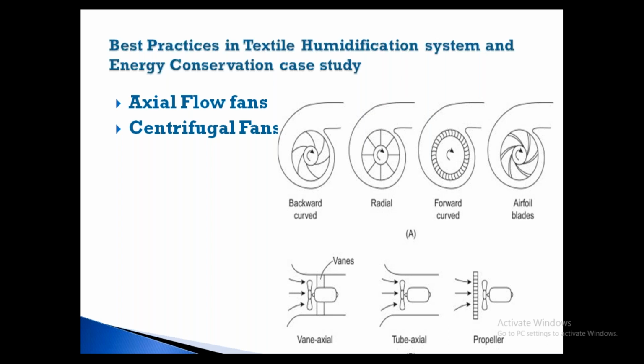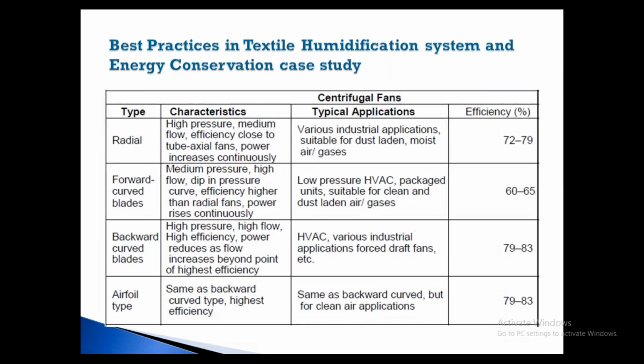If you take the axial flow fans, we have three types: one is vane axial, then tube axial, then propeller fans. Propeller fan is least efficient, vane axial is the most efficient one. So the selection of the fan is important, not only for finding the power of the HVAC plant. You would have seen two identical plants, and you would have taken the readings and power calculation for the particular mill or process. But you need to note which type of impeller fans they used. It is not only that the factory was better in efficiency. We have to point out which type of fan they used, where there is a possibility of increasing the efficiency.